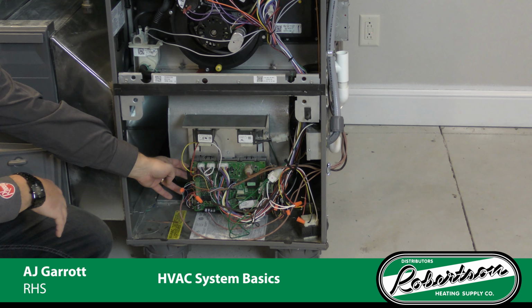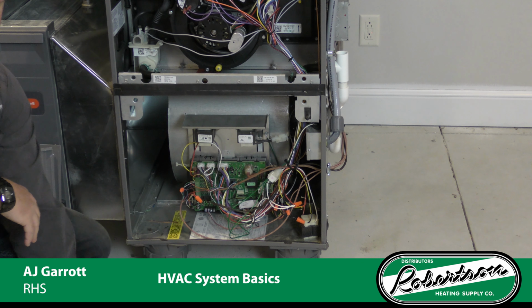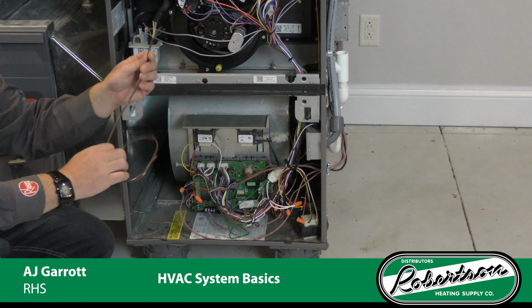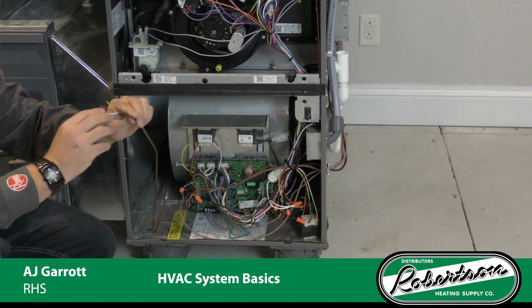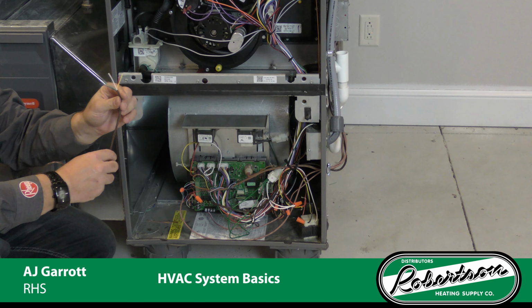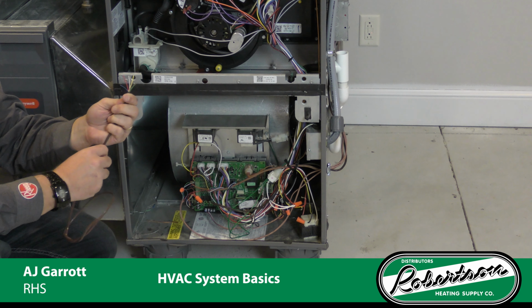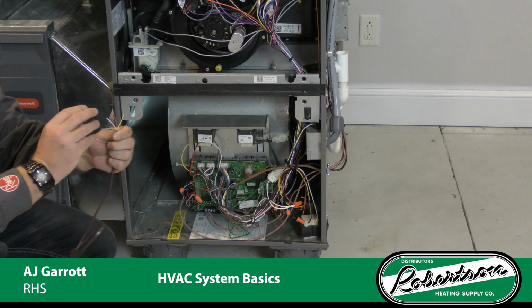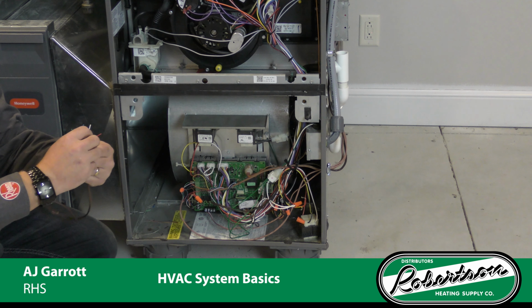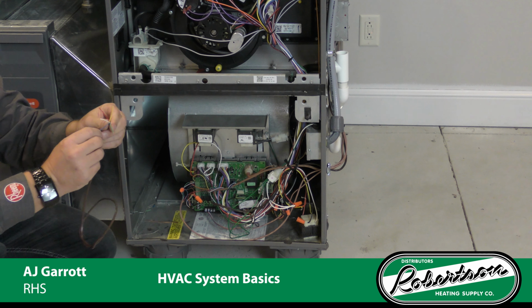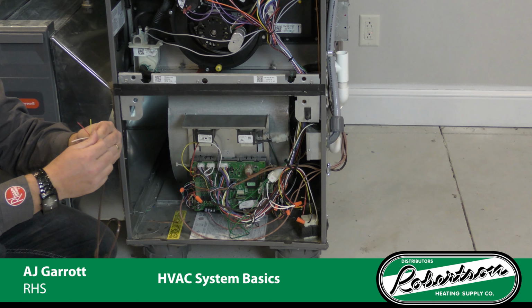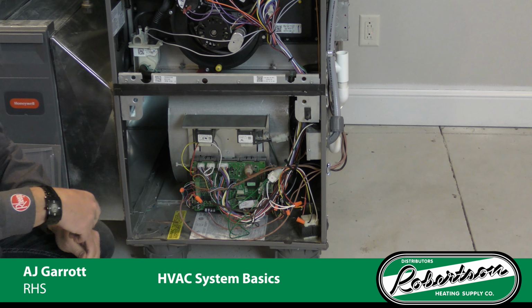This is a control board down here where we see our thermostat wire comes down into. This is thermostat wire, 18 gauge, again like we talked about, and this has actually 5 wires in it, so it's a 5 conductor. The wires are color coded to help with ease of application and installation, so we know what wire is connected to what terminal in the board and at the thermostat.